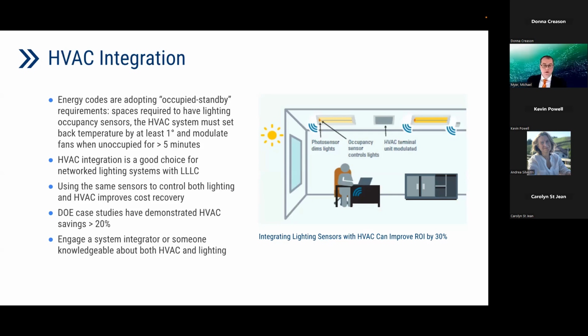So HVAC integration. The idea of HVAC integration is you have spaces that are designed from a mechanical point of view, and they cool and they provide air and those types of things. But by using the occupancy information from the lighting system, we can actually help inform the mechanical system. While we thought the building, often many of those offices were empty. Occupied during the day, they may be unoccupied for an hour and a half while everyone's at a meeting.